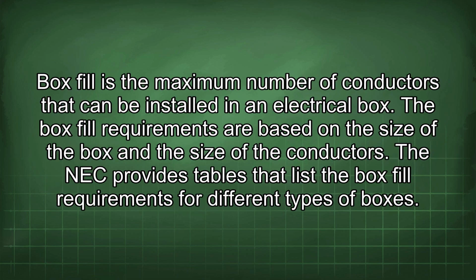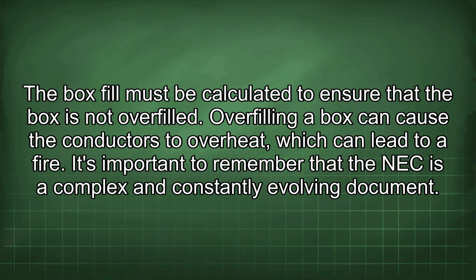Box fill is the maximum number of conductors that can be installed in an electrical box. The box fill requirements are based on the size of the box and the size of the conductors. The NEC provides tables that list the box fill requirements for different types of boxes. The box fill must be calculated to ensure that the box is not overfilled. Overfilling a box can cause the conductors to overheat, which can lead to a fire.